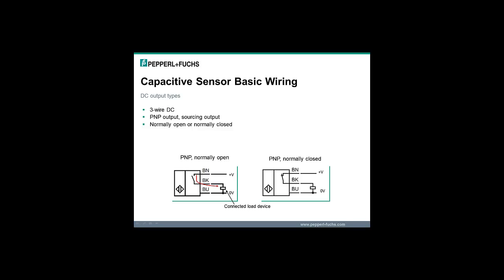The most common capacitive sensor output type is the 3-wire DC PNP output. As shown in the diagram, this output supplies voltage and current to the connected load. For the normally open PNP output, the load is connected to plus voltage when the sensor is activated. For the normally closed output, the load is connected to plus voltage when the sensor is deactivated.